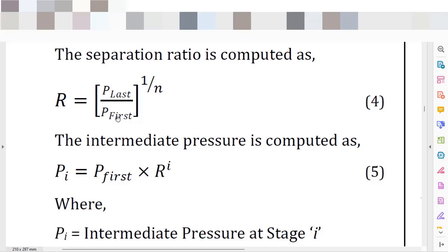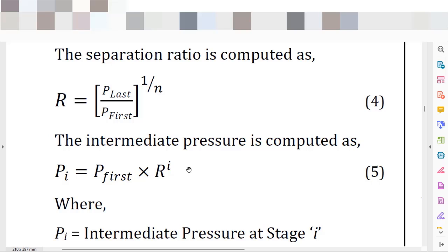Once you have calculated the global pressure ratio, to find the interstage pressure ratio you apply the equation where the global pressure ratio raised to the power of 1 divided by the number of stages gives you the interstage pressure ratio. With this result, you can define the discharge pressure of each stage: the inlet pressure multiplied by the pressure ratio gives the discharge pressure of the first stage, and that discharge pressure multiplied by the pressure ratio gives the discharge pressure of the second stage.